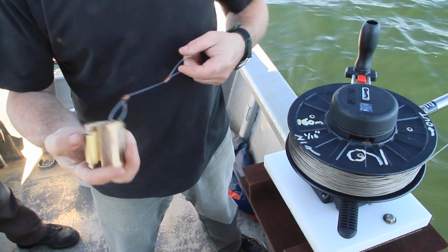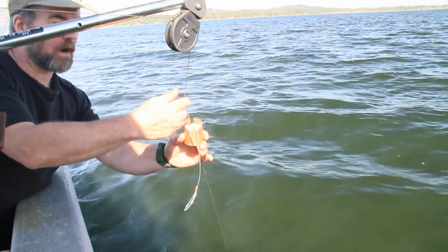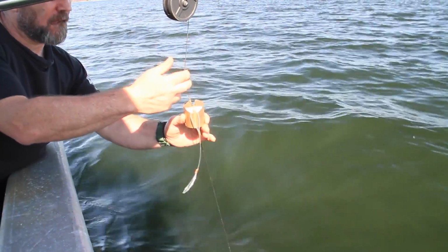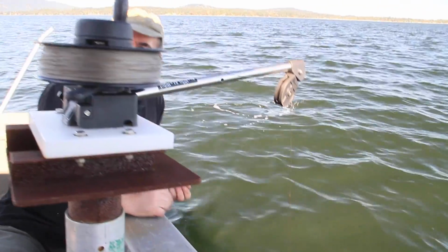The lanyard here is just to pick it up. Okay, so what we'll do is slip it around the wire. Hold above the wire with your finger and let it go. It drops at about 1 meter a second. It's going to hit the thing and there's going to be a thunk, and you can feel it on the wire. You saw this actually moved as well.